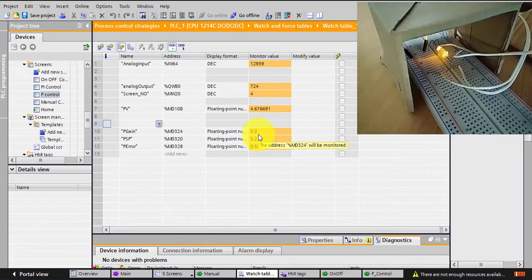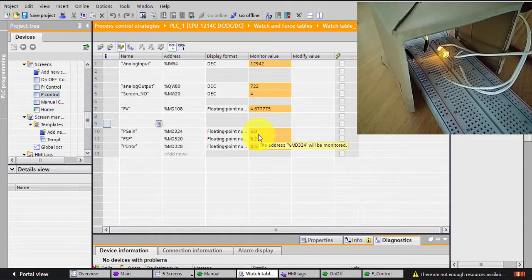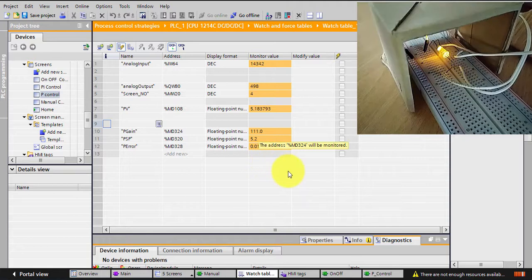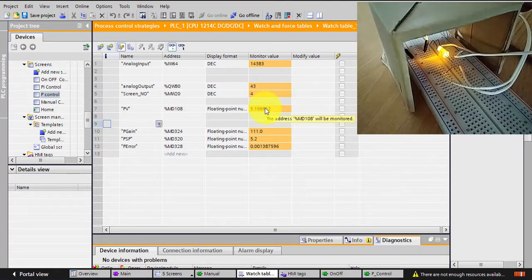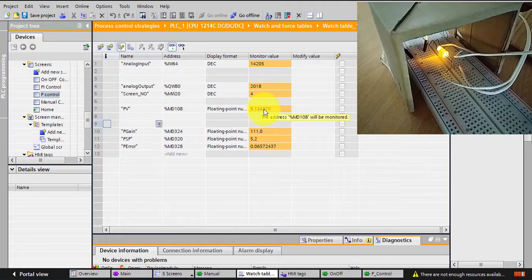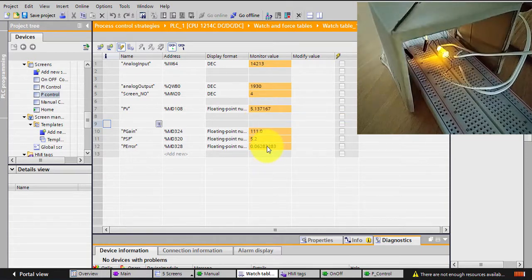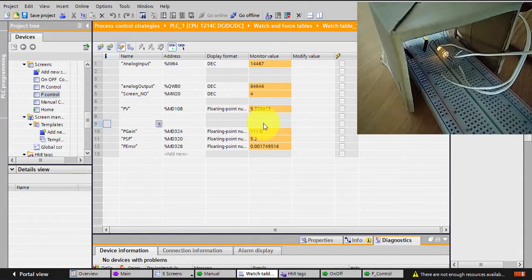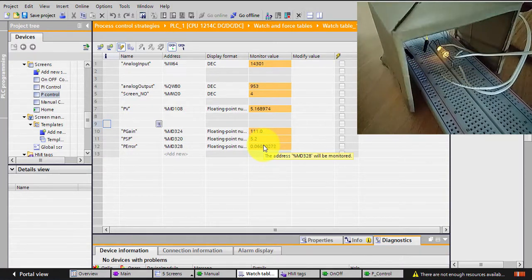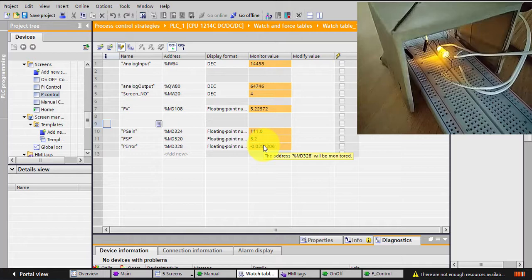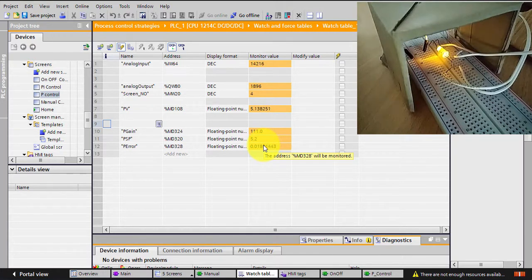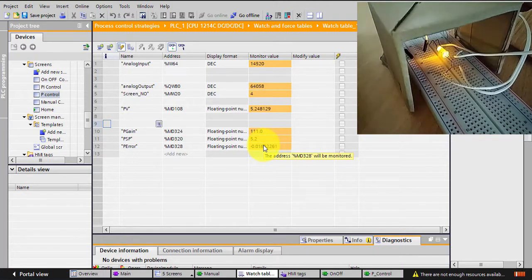Now since we are here, let's check what will happen if I enter a very high value for a P gain, so I will enter a value of 111. And as you noticed, my PV is actually going around the set point.